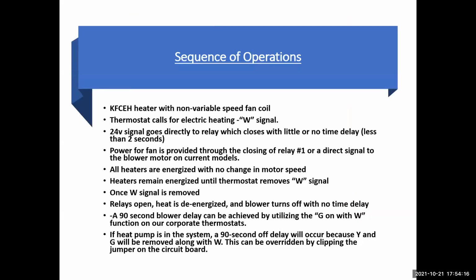Sequence of operation on the KFCEH heaters with a non-variable speed fan coil. Thermostat calls for electric heat, W signal, 24 volt, goes directly to the relay, which closes with little or no time delay, less than 2 seconds. Power to the fan is provided through the closing of relay number 1, or on the new FB4s with the X13 motors, ECM motors, there's a direct signal to the blower motor. All heaters are energized with no change of motor speed. Heater remains energized until the thermostat removes the W signal. Once the W signal is removed, relays open, heat is de-energized, the motor shuts off with no time delay.